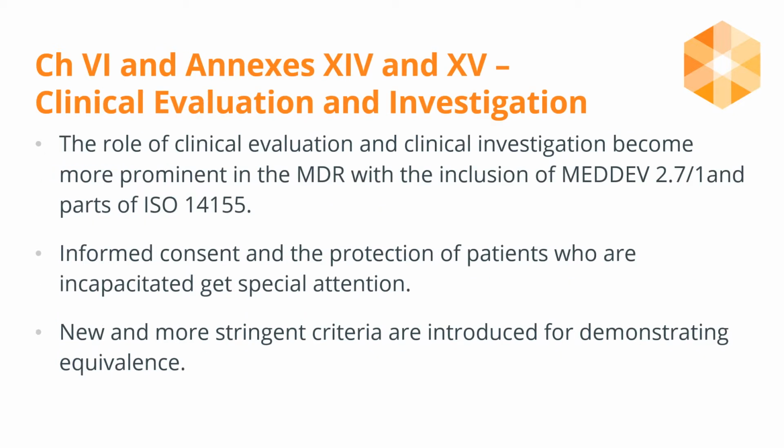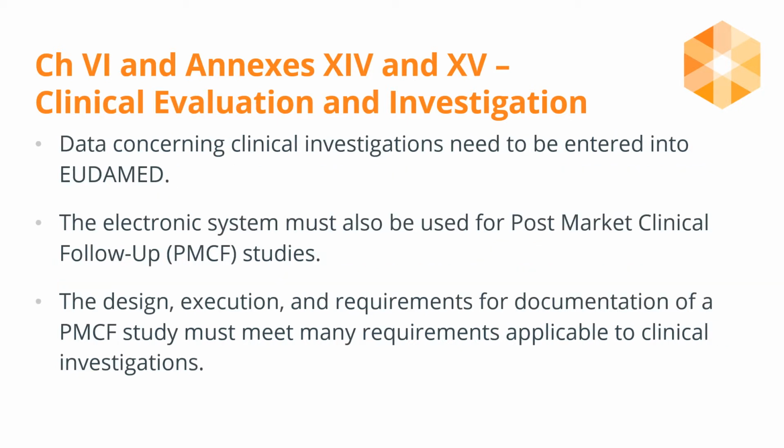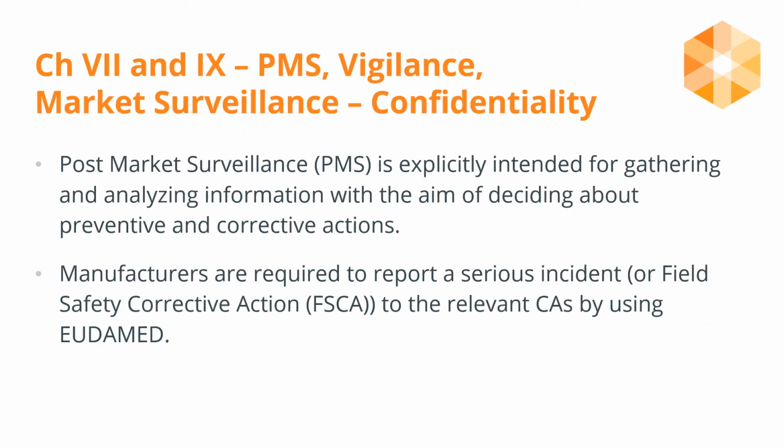Demonstrating equivalence will now fall under more stringent criteria. The informed consent and protection of vulnerable populations gets special attention, and the role of clinical evaluation and clinical investigation has become more prominent. This data system must have data concerning clinical investigations entered, and it must also be used for post-market clinical follow-up studies. And the design, execution, and requirements for such studies must meet many requirements applicable to clinical investigations. Post-market surveillance will be used for deciding preventative and corrective actions, and manufacturers are required to report serious incidents.